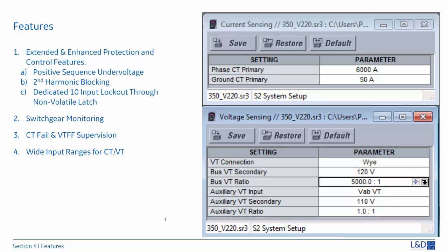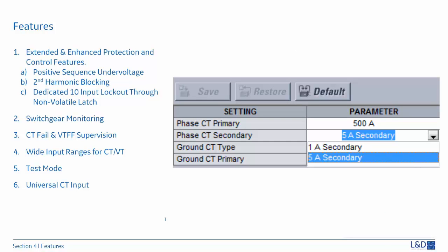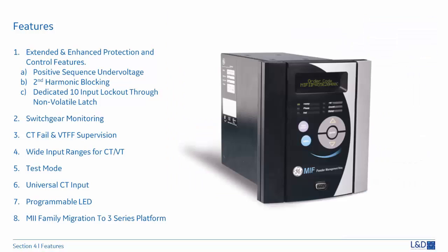CT fail supervision and VT fuse supervision are provided to avoid undesired operation of protection elements. Wide input ranges for CT/VT: the 350 phase CT primary is up to 6,000 amps, and VT ratio range is 5,000, meaning the permissible primary VT voltage can reach 550 kV. The test mode can test front panel LEDs and outputs without external test equipment. A universal CT is available for the non-draw-out relay with software-selectable CT secondary, providing less hardware dependency and more flexibility for future design changes. Programmable LEDs are available so users can customize the LED display. MII family migration to the 3 Series platform is simplified with retrofit tools and setting file conversion in the software.